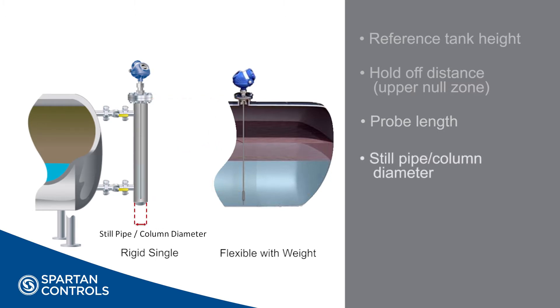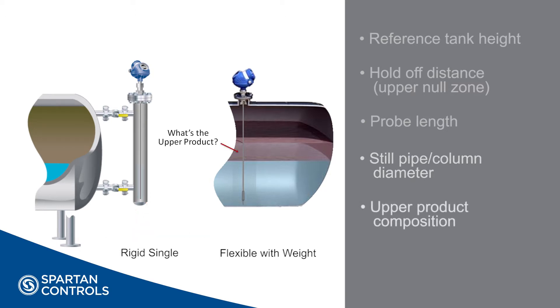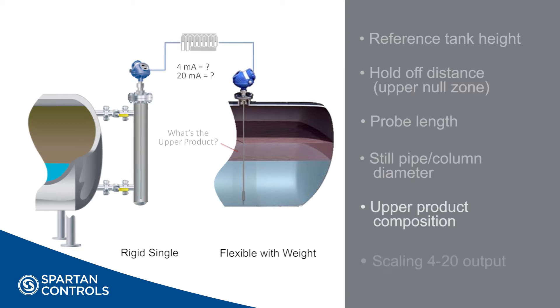Column or pipe diameter is the approximate inner diameter of the still pipe or column the antenna is to be mounted in. If this is an interface measurement application, note what the upper product will be as this will affect the measurement. The last thing we want to note is the scaling values we want to be using for our 4 to 20 milliamp analog output signal.